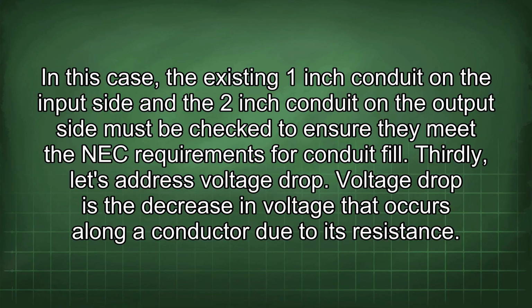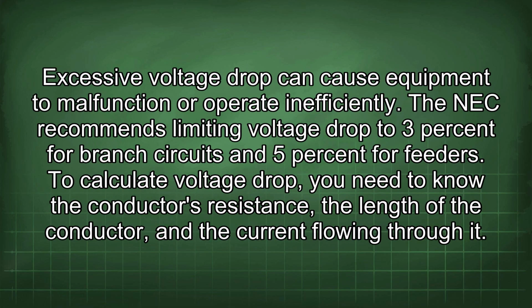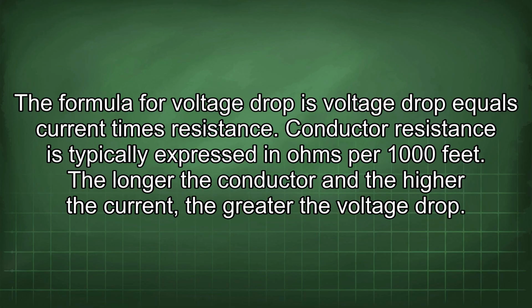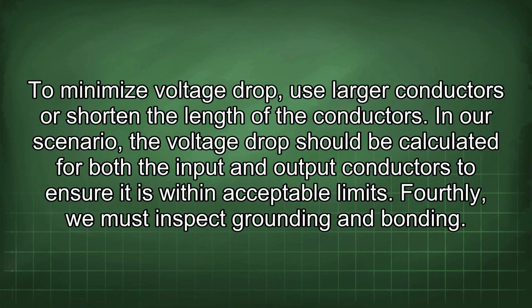Thirdly, let's address voltage drop. Voltage drop is the decrease in voltage that occurs along a conductor due to its resistance. Excessive voltage drop can cause equipment to malfunction or operate inefficiently. The NEC recommends limiting voltage drop to 3% for branch circuits and 5% for feeders. To calculate voltage drop, you need to know the conductor's resistance, the length of the conductor, and the current flowing through it. The formula for voltage drop is voltage drop equals current times resistance. Conductor resistance is typically expressed in ohms per 1000 feet. The longer the conductor and the higher the current, the greater the voltage drop. To minimize voltage drop, use larger conductors or shorten the length of the conductors.